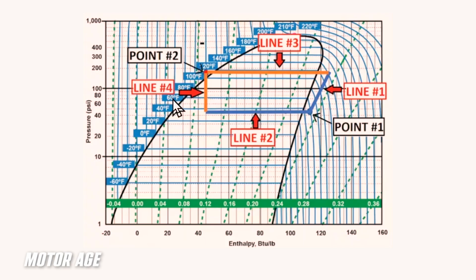So this is an instruction on how to plot the information. This very first point you see here in the lower right portion of this graph represents the inlet temperature and pressure. In other words, pressure on the low side entering the compressor and the correlating temperature. The temperature with our temperature probes is just above freezing, and our pressure is just above 42 psi, give or take. Now from there, we plot our point and we draw a line projecting outwards parallel to this green line right here.